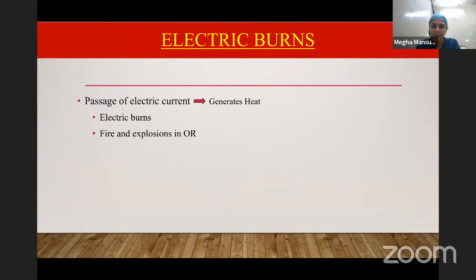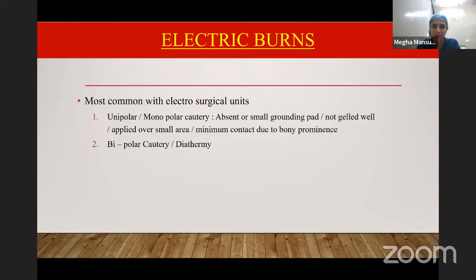Now coming to electric burns. We know that passage of electric current generates heat, and this heat generated can cause either electric burns or fire and explosions in the operating room. Electric burns are most common with electrosurgical units. These can be unipolar or monopolar cautery, and bipolar cautery or diathermy.